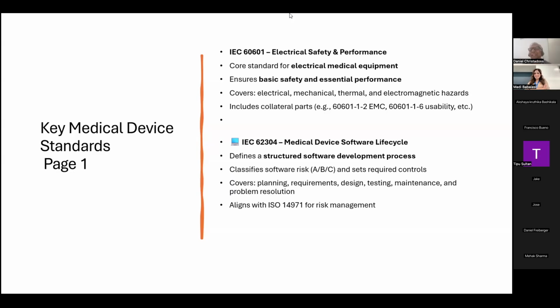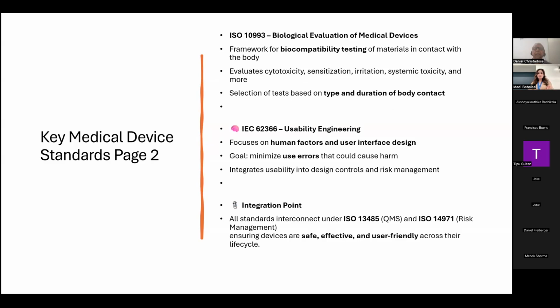They'll keep updating the code on the machine. When you do this, you don't have any traceability. Why was it changed? What is the reason it was changed? So IEC 62304 will give you all the standards for how you make that happen. And the next one is what I can try to say.